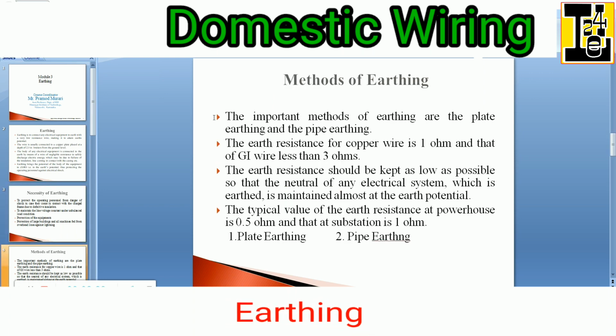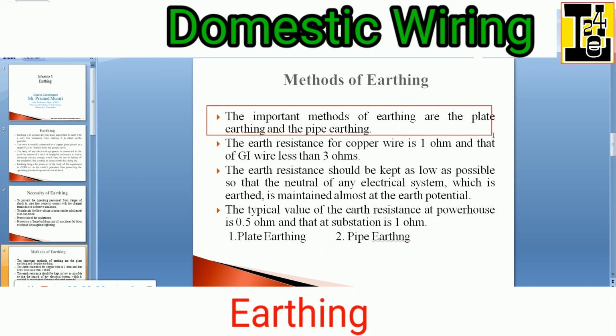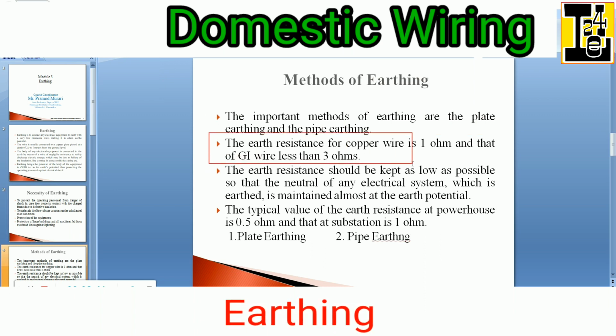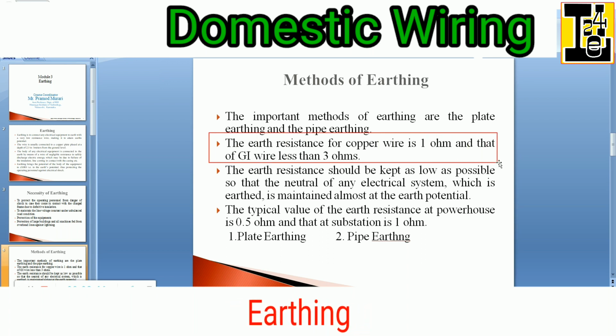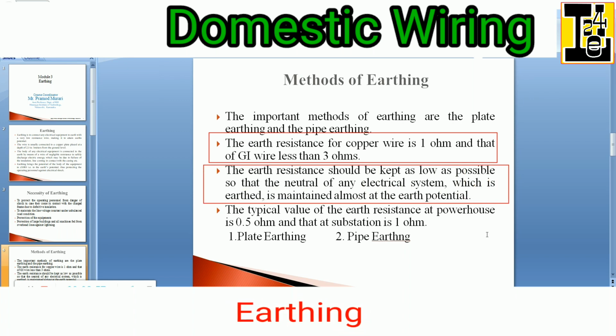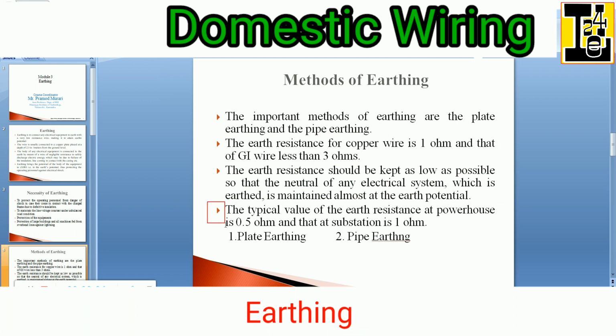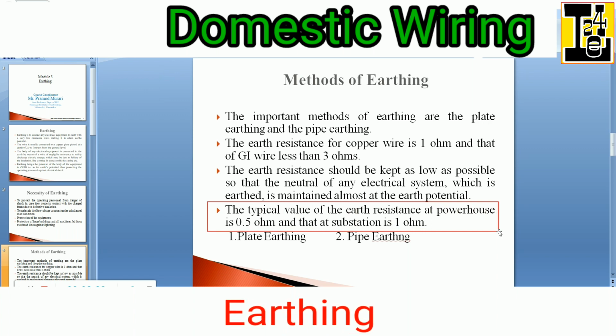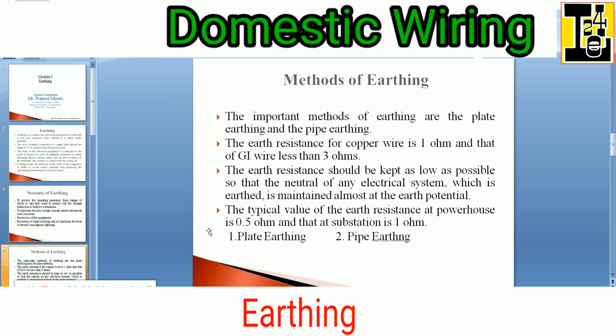What are the methods of earthing? The important methods of earthing are plate earthing and pipe earthing. The earth resistance for copper wire is 1 ohm and that of GI wire is less than 3 ohms. The earth resistance should be kept as low as possible so that the neutral of any earthed electrical system is maintained almost at the earth potential, that is, zero potential. The typical value of the earth resistance at a powerhouse is 0.5 ohm and that at a substation is 1 ohm. There are two types of earthing which we are going to discuss. The first one is plate earthing and the other is pipe earthing.